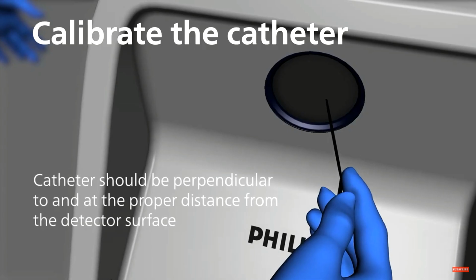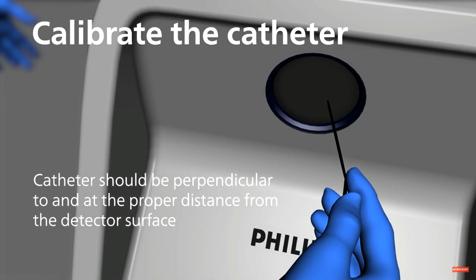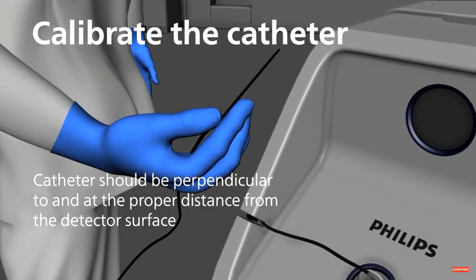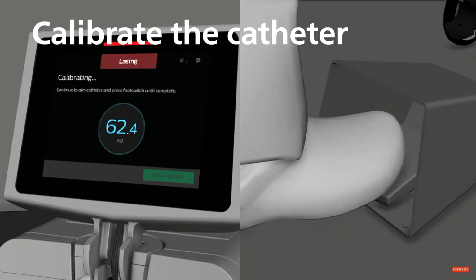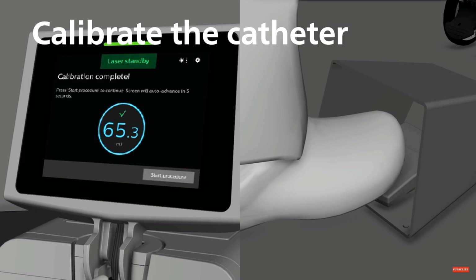The system may not pass calibration if the catheter is not perpendicular to and at the proper distance from the detector surface during calibration. While calibrating, the system will display its progress. The circular progress bar will fill as calibration progresses. Energy readings will be displayed during the process. Once calibration is complete, the system will display the Calibration Complete screen. The calibration energy is displayed to compare the calibration energy reading with the energy range for the fiber optic catheter selected. See catheter package for appropriate ranges.